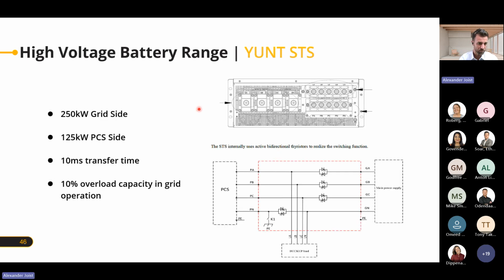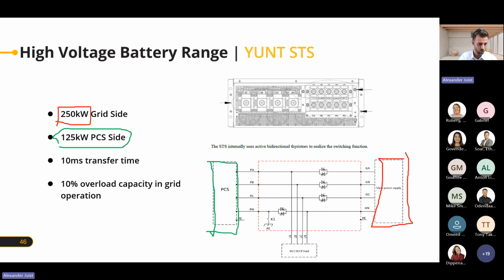If we look at the STS, everyone always asks the question, why does it say 250 kilowatt STS? You will see it always the same. All the manufacturers call it 250 kilowatt because the main power supply coming from the grid on this side is 250 kilowatt. So this means 125 kilowatt from the PCS side, 125 kilowatt on this side, and also 125 kilowatt on the backup loads, right?